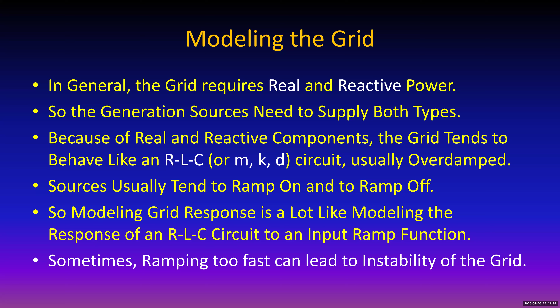The result is you need to smooth out rapid changes, and there are ways to do that. Something less obvious is that generators aren't designed to absorb power. If you have a rotating generator and try to run electricity back into it, it behaves as though you're trying to turn it into a motor, and the prime mover isn't happy about that. So we need to be careful not to generate so much power that the renewable source tries to run the generator backwards. If wind or PV tries to feed power into the generator, we have to do something about that so it doesn't happen.